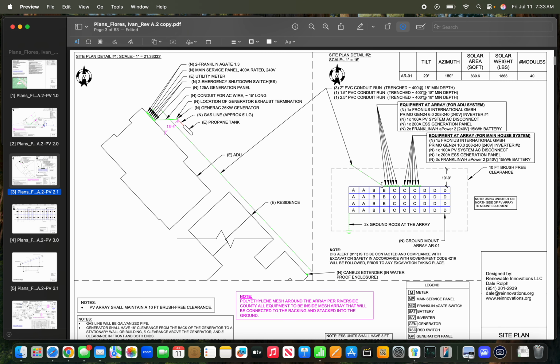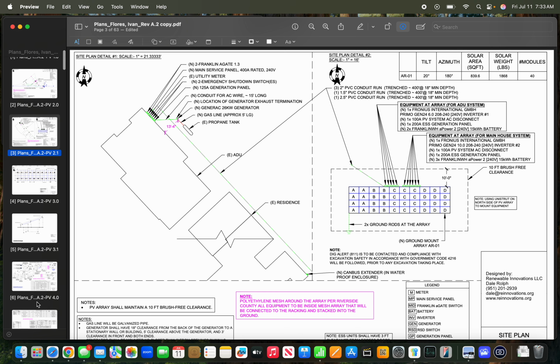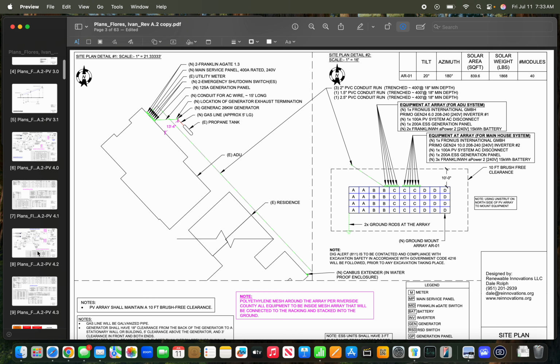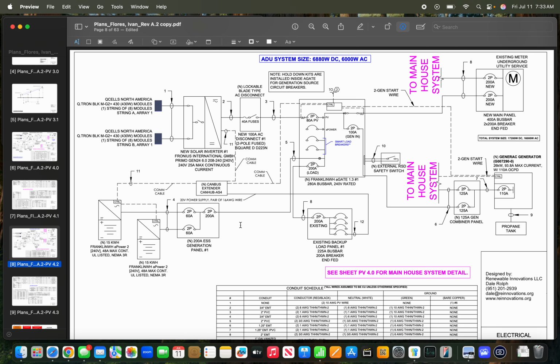The batteries are on the outside, so the homeowner could add more batteries on either side as needed over time, and they don't have to do anything. The electrician would just connect another battery to the racking, wire it to the sub panel, and recommission the site to add that battery. They wouldn't need to do anything out of the ordinary, and they don't have to pull any new wire. I designed this for future expansion, something many companies like to promote that they do, yet fail to do successfully.